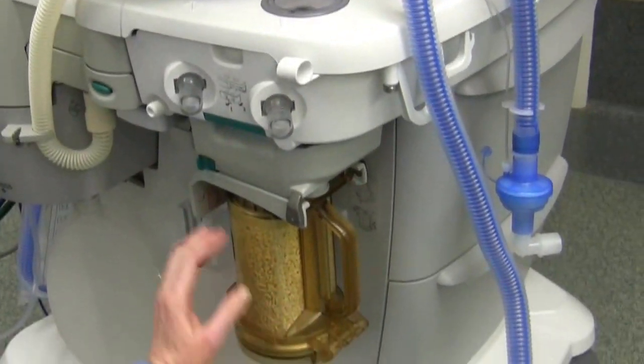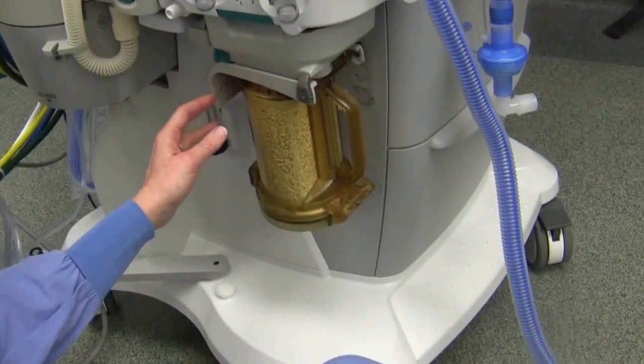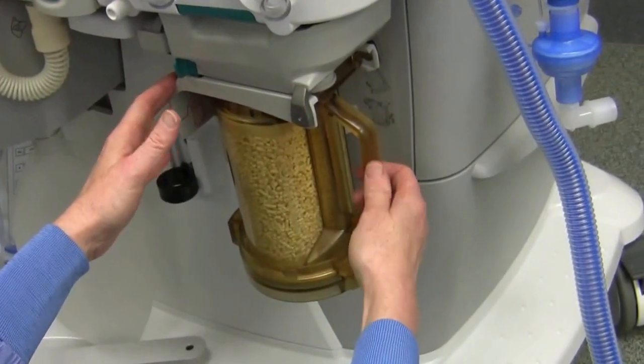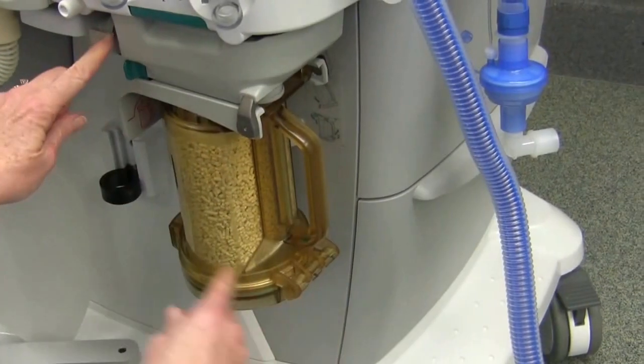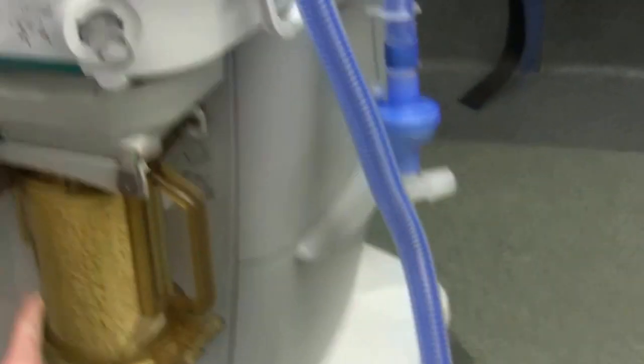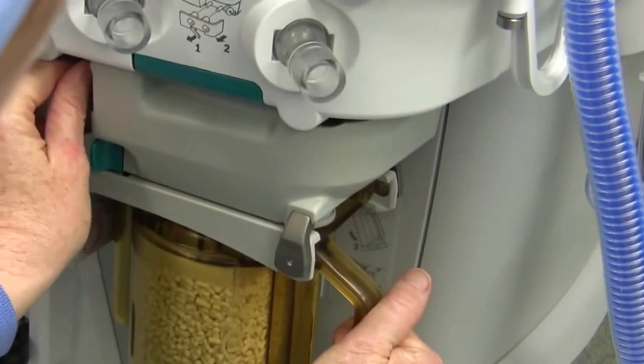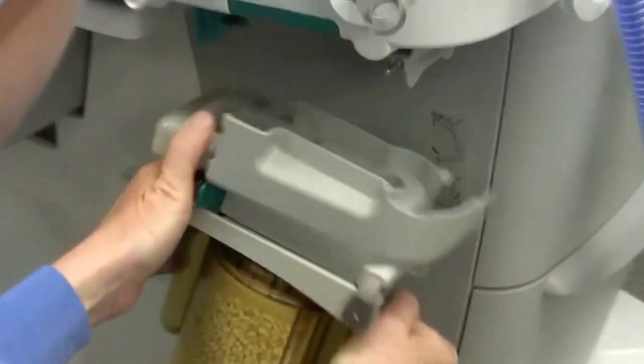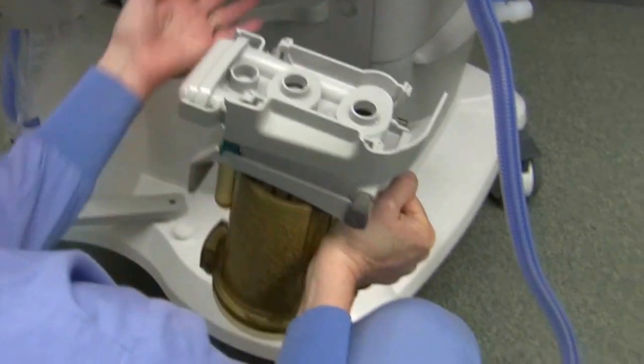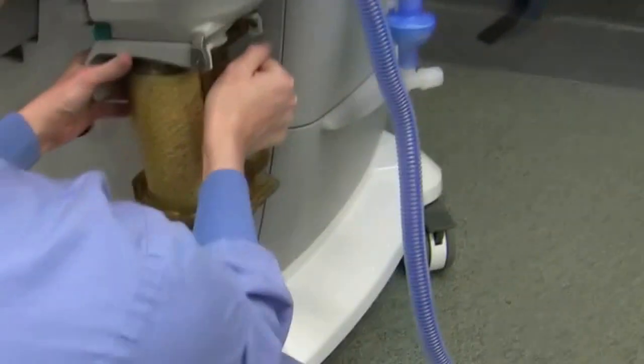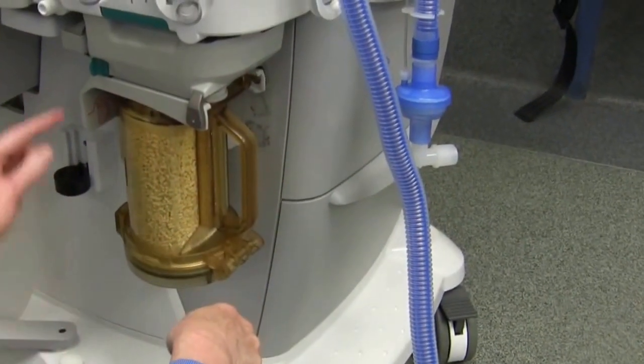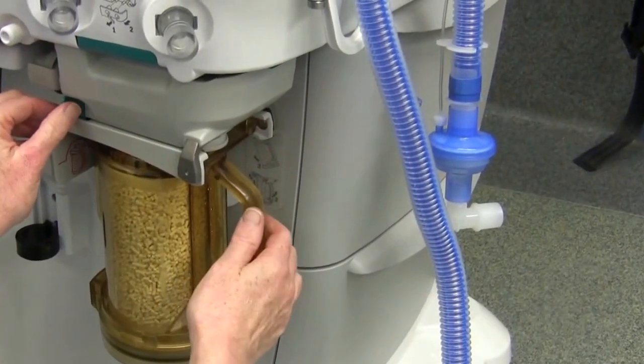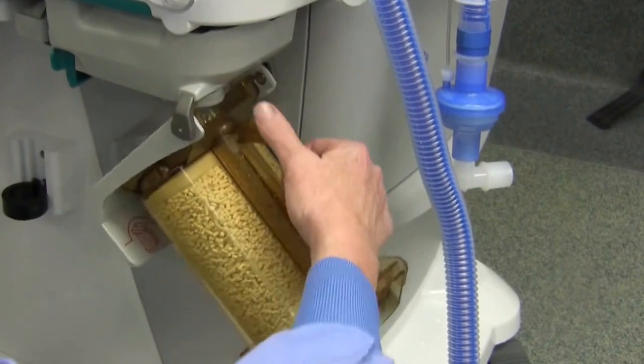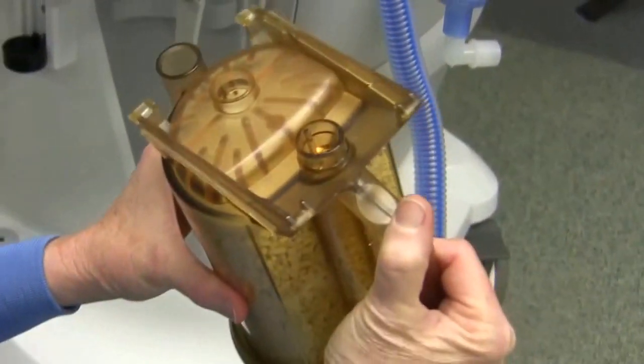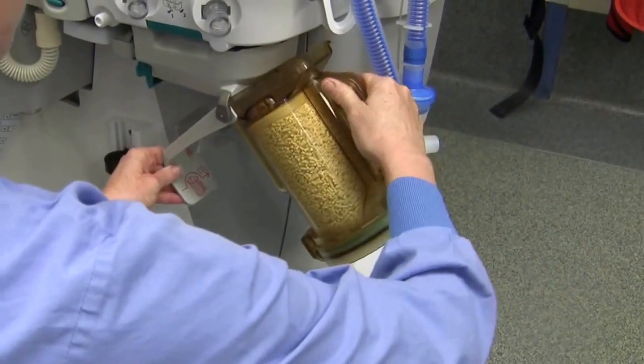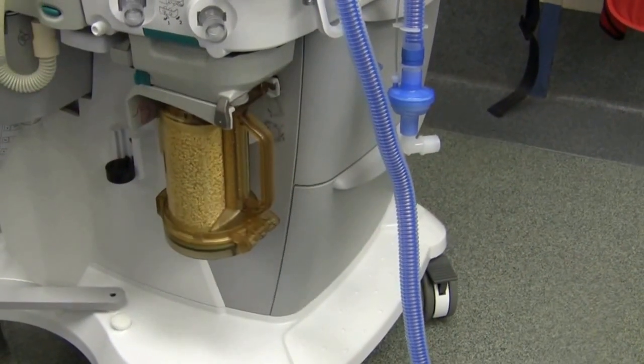This is your CO2 absorber, and these machines come with an easy refill. What that means is you can take it out while the case is running. You have two green buttons here. The top one will take the entire unit off. It's not the one that we want you to really do. It takes the entire unit off. It's safe to still continue giving an anesthetic, but this is very cumbersome to put back in. The lower one is the easy fill. What it does is it releases this, you pull it out, you get a new one that's already pre-filled, you just slide this back in and clip it up.